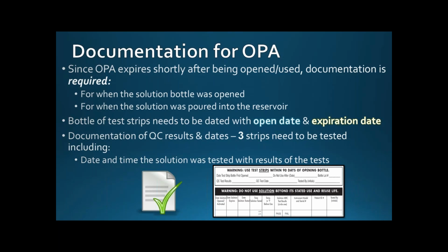And then you have the date of your test strips that you have to track. And then, like I said, your QC results for your test strips. And then making sure that you have documentation. You have to be able to link the cleaning of your instrument back to the scope or device that you've done high-level disinfection on. So there's a lot of different things that it takes in terms of making sure that you are documenting appropriately. There's a lot of opportunities in there to make sure that you're meeting regulatory compliance and following proper high-level disinfection.